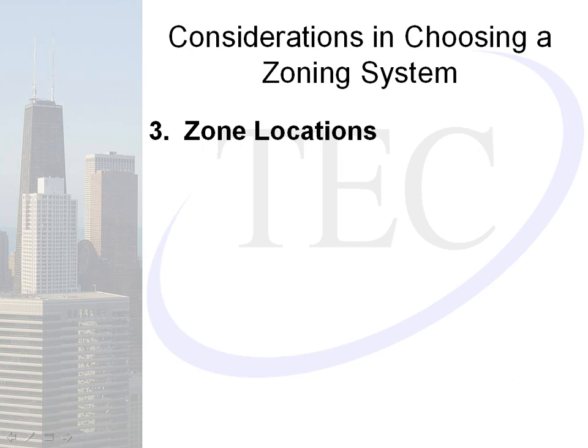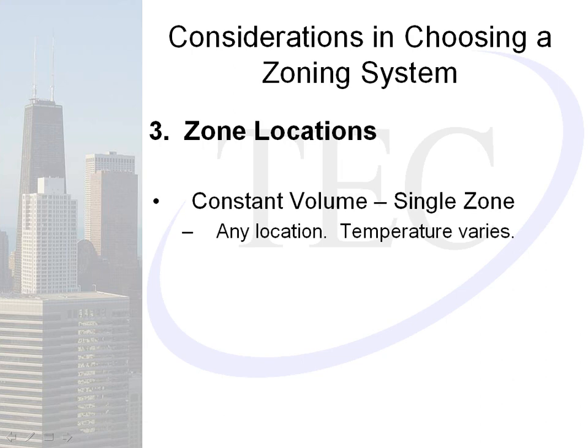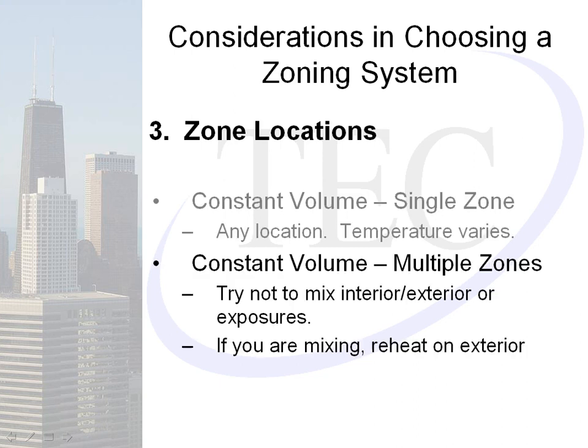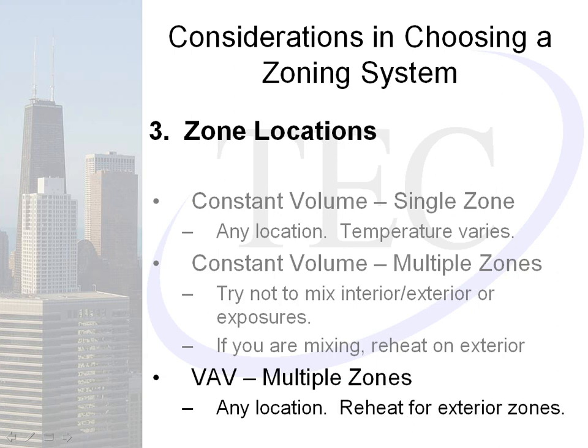The third consideration is zone locations. For constant volume single zone, any location works as temperature will vary accordingly. For constant volume multiple zones, we try not to mix interior and exterior zone exposures, as there will be significantly different load patterns. It's best to keep exterior zones on one system and interior on another. If mixing, you definitely want to put reheat on your exterior zones. For VAV multiple zones, any location works, but reheat for exterior zones is a definite.